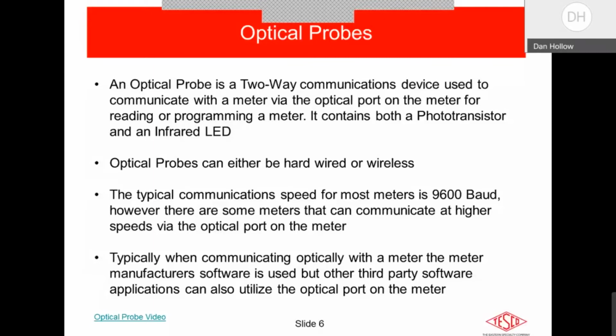Whereas some probes in the early days would only work with a particular meter manufacturer's device. So once the universal optical probes came out, it made it easy for the utility to use meters from multiple vendors and be able to communicate with them with the vendor software and that universal optical probe.